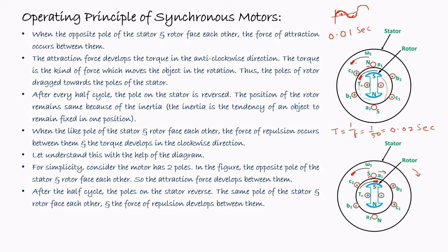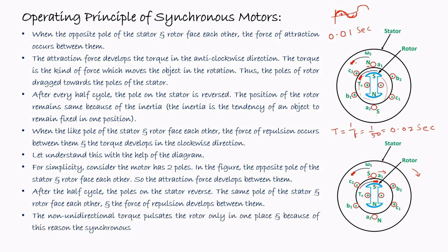So due to this frequent change in polarity of the stator, the rotor cannot rotate in a particular direction. Basically the rotor will be continuously vibrating in its position. So no unidirectional torque will be developed on the rotor. It will only pulsate in its position. And because of this reason, the synchronous motor is not a self-starting machine.